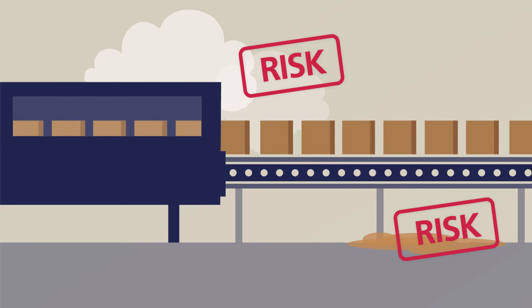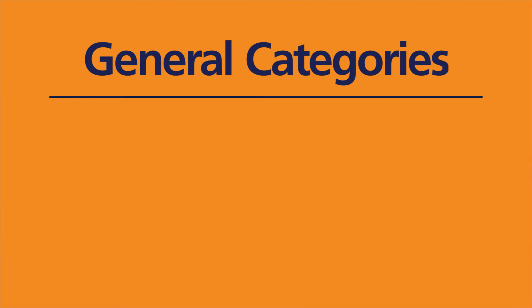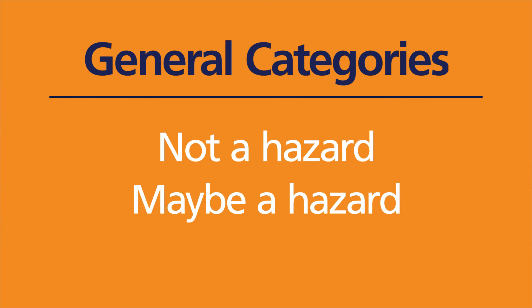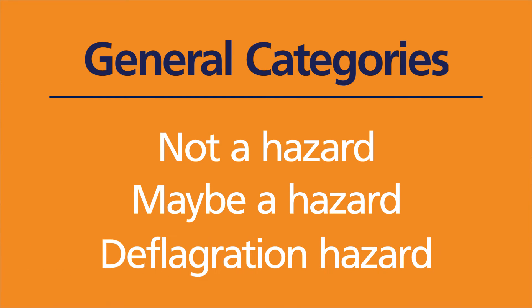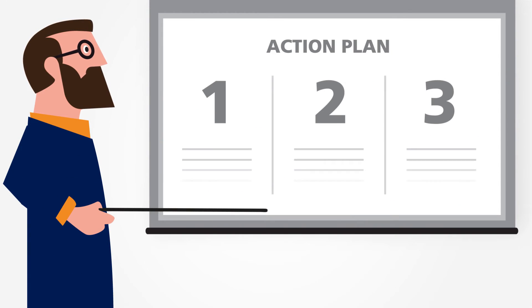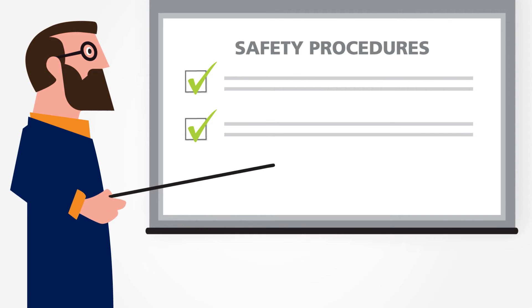Your DHA should group all locations in your facility into three general categories: not a hazard, may be a hazard, and deflagration hazard. This will help you prioritize the management of hazards, educate workers about those hazards, and create safe, proper procedures and train workers on how to follow them.